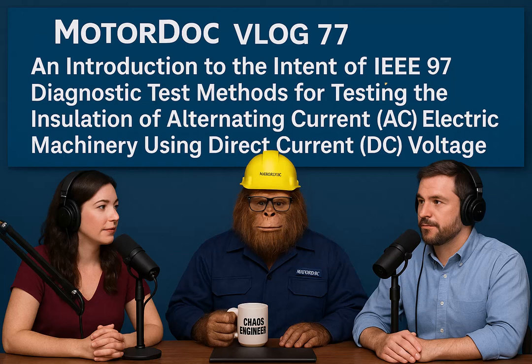What about environmental factors like temperature or humidity? Huge influences. Temperature significantly affects the insulation's resistivity. The guide suggests correcting measurements to a standard temperature like 40 degrees C if you can, like they outline in IEEE 43. Or at least be consistent. Yes, at the very least. So especially for tests like IRP where you're trending results over time, you absolutely need to perform the tests at a consistent temperature each time.